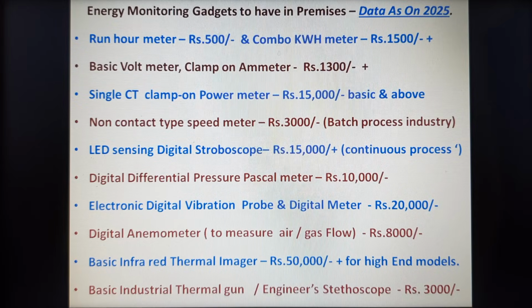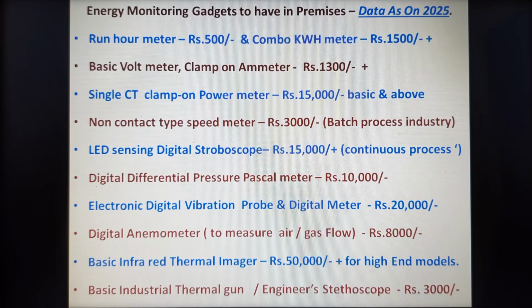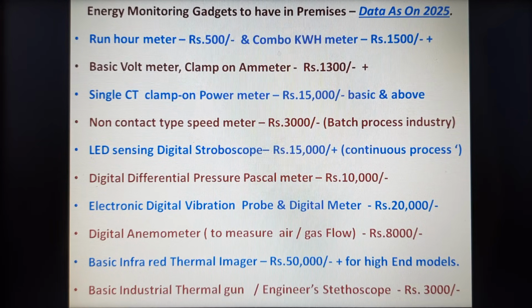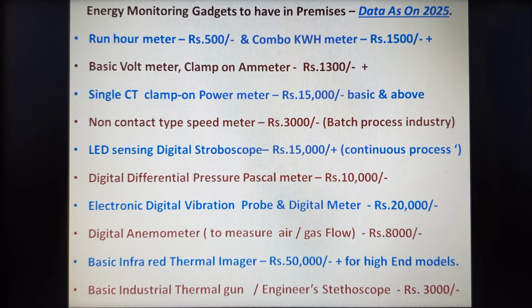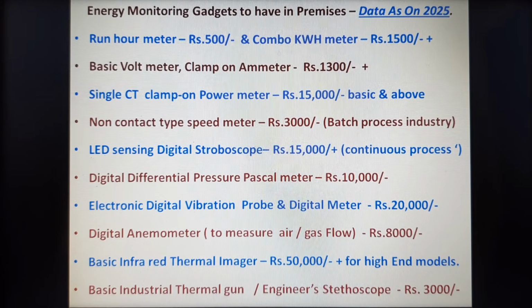It's a single insertion type, and definitely you can know what the compressor is delivering, whether 1 CFM is delivered at 150 watts, or 1 CFM is delivered at 200 watts, or 1 CFM is delivered at 250 watts. All this can be checked if you have both the input kWh meter and the output flow meter, especially on the compressed air. Then comes the basic infrared thermal imager.